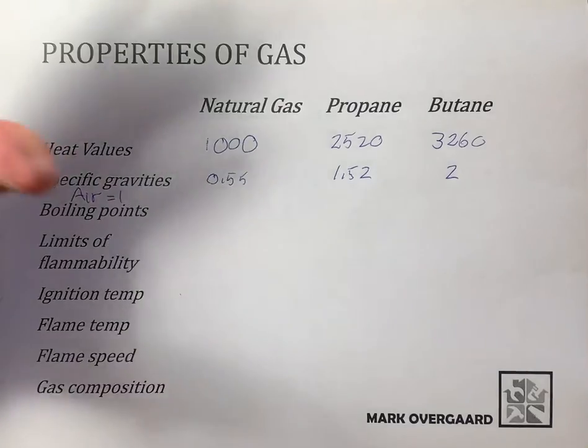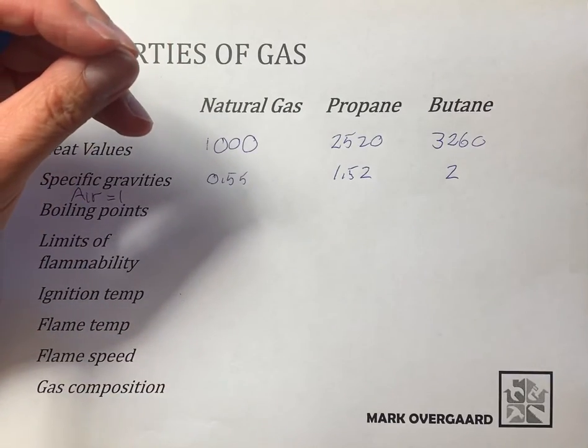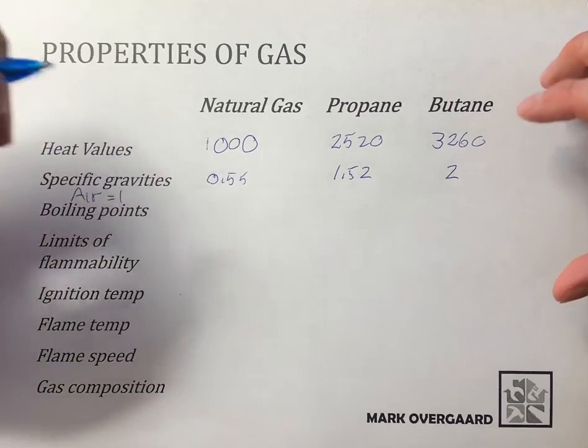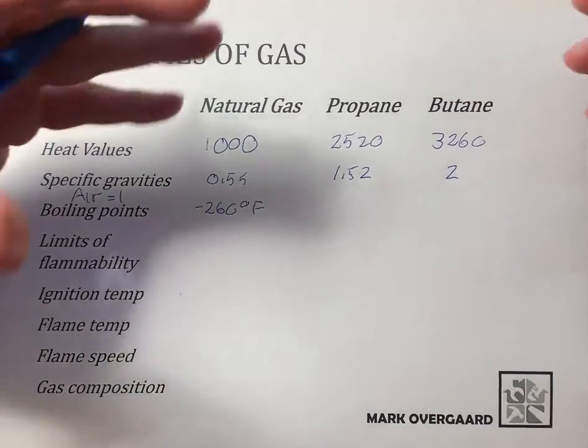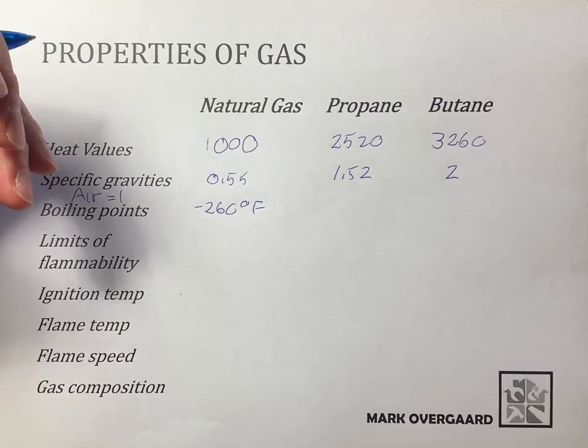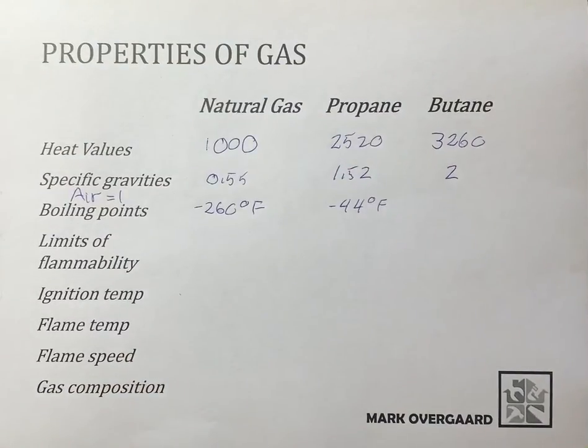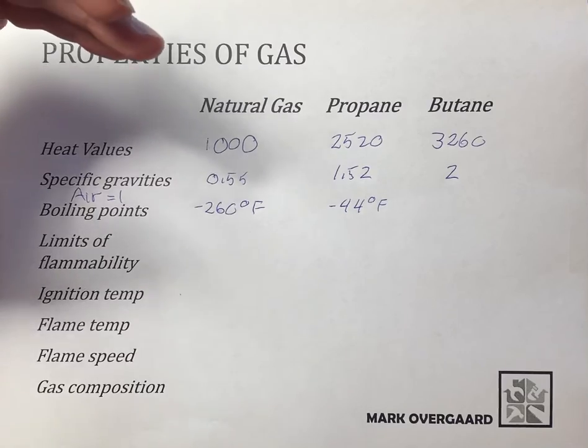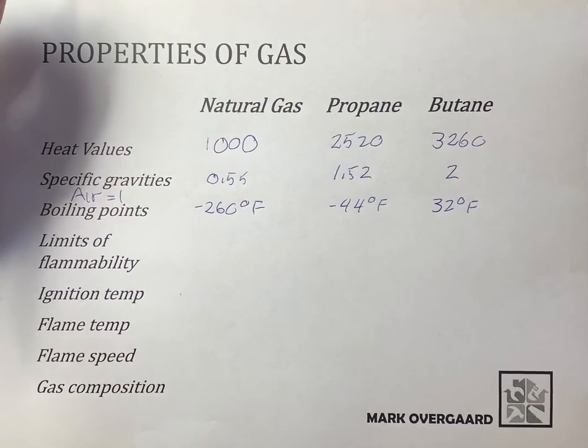Boiling points — where does each gas go from a liquid to a vapor? Water, for reference, boils at 212°F or 100°C. For natural gas it's at negative 260°F, which means natural gas is almost always in a vapor state wherever we find it — it only becomes liquid below negative 260°F. Propane changes over at minus 44°F, so in very cold conditions propane can struggle to vaporize. Butane is 32°F, so above freezing it's a vapor; below freezing it stays liquid.